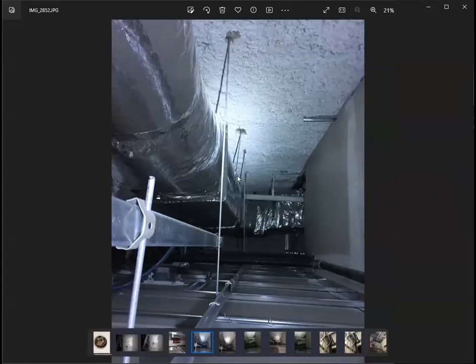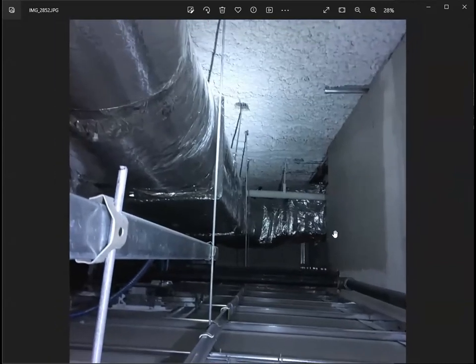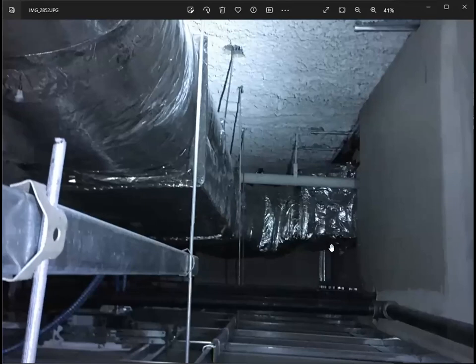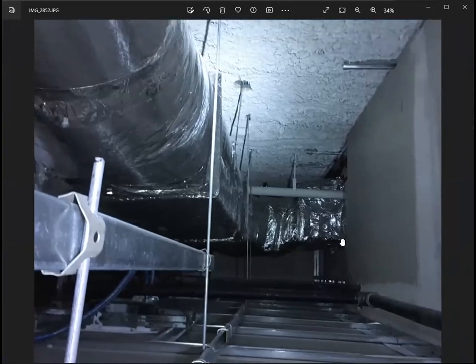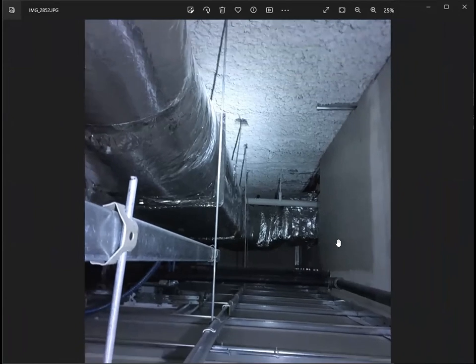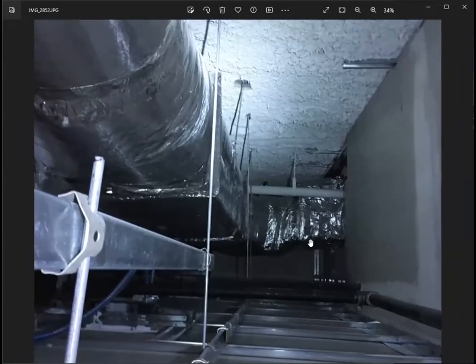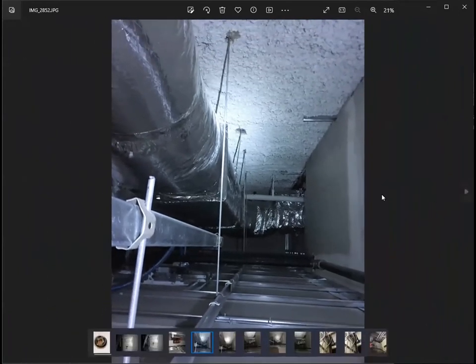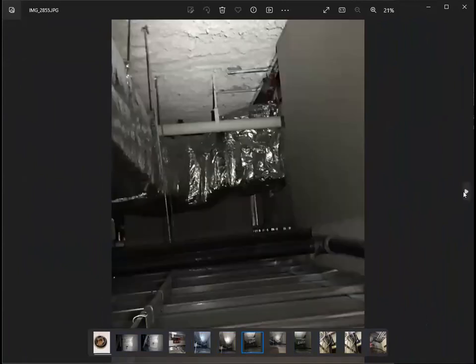Right here, I probably took a photo of the insulation of the ductwork. This falls under the energy inspection. You need to insulate the ductwork, especially if it's conditioned air supplying a particular room. And if this wall is fire rated, this ductwork penetration should also be protected by a fire damper and retaining angle around it. If not, they have the option of insulating it with a fire-rated insulation.